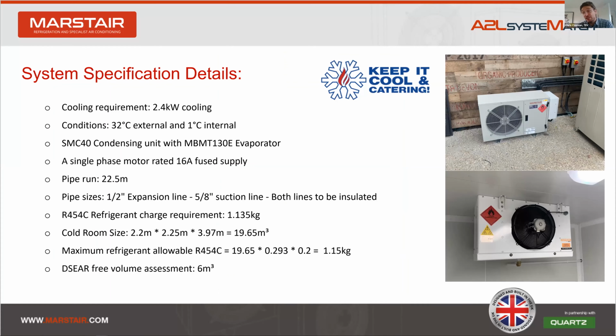So the story goes, I was first contacted by Charlie at Keep It Cool because he'd seen one of my articles about the potential use of A2Ls in cold rooms. Charlie informed me that he and Rutherford would be interested in trying out an alternative green solution to CO2 refrigerant. So we had a look at it together. It was about 2.4 kilowatts, fairly standard refrigeration conditions, on a 22.5 meter pipe run, with charge levels against the room size, and everything looked good. So we agreed to move forward with the project.